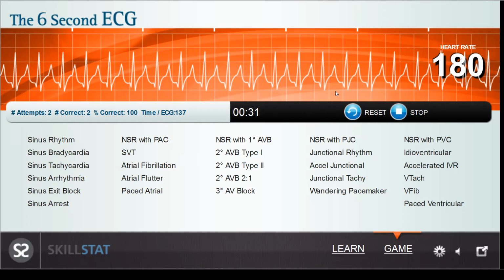Remember, whenever you cardiovert, you have to hit the sync button, the synchronized button. That's the main difference between cardioversion and defibrillation, is that you hit the sync button. What happens when you hit the sync button is that when you hit the button to defibrillate, there's going to be a pause. The machine is not going to shock them right away. Why? Because it's waiting for the next QRS. It's going to shock on the R wave. Why? Because if it shocks on the T wave, the patient will go into VFib.